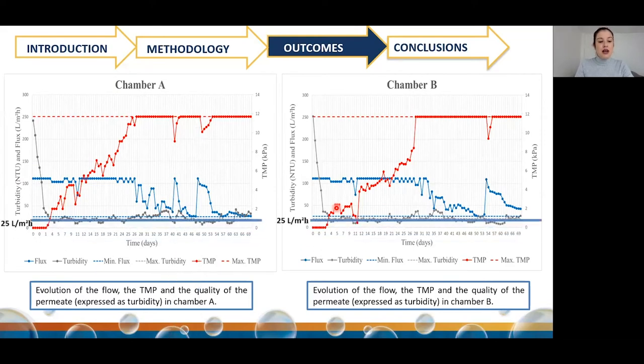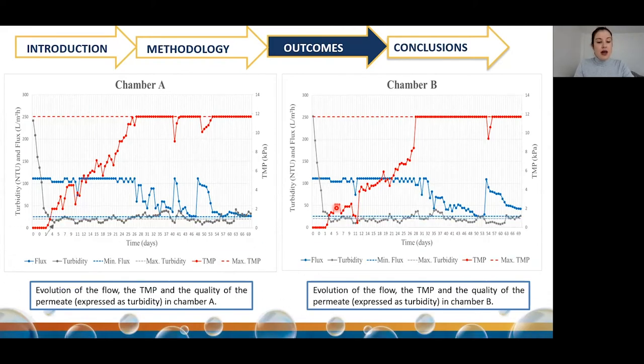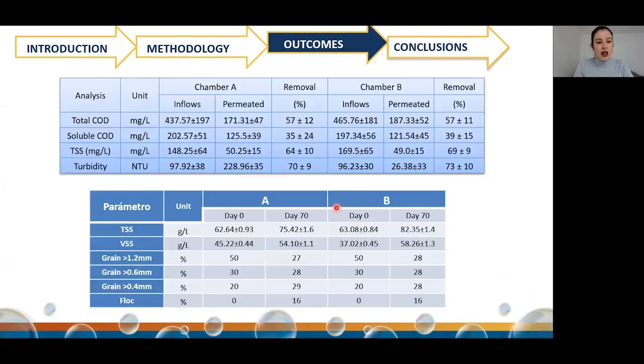The minimum flux achieved in both chambers was above 25 L/m²h, still an acceptable value compared to those reported in studies with conventional anaerobic membrane reactors. The permeate quality measured as turbidity showed fluctuations between 7 and 39 NTU once the dynamic membrane was formed. The sludge in both chambers was washed by applying an upward water flow to eliminate accumulated floc. This washing was performed with the filtration modules inside the chambers, so the fouling layer of the dynamic membrane was not expressly removed. Daily system monitoring evaluated turbidity, total suspended solids, and total and soluble COD of collected samples.